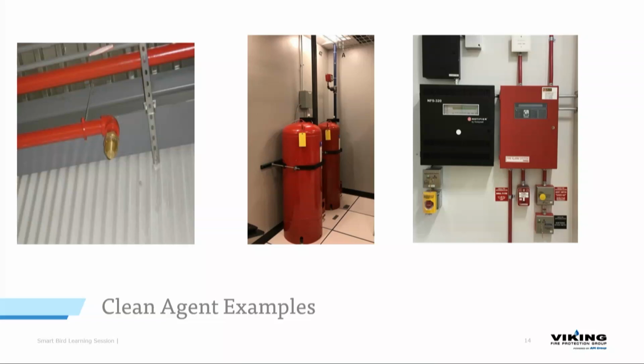Couple tanks here. We have a control room. I threw this picture in there because I think it's good to note that gas is very specific to the compartment that it's in. One of these systems is feeding this room. The other one is feeding below the raised floor. So we'll have a completely separate system that feeds all that cabling that goes underneath the floor. In each situation, we do have a fire alarm panel and a panel that is set up for the releasing and alarming. Basically, if there's a fire, we can release this automatically if we need to. And in most control rooms, you're going to have a pull station and an automatic release for the gas suppression systems.